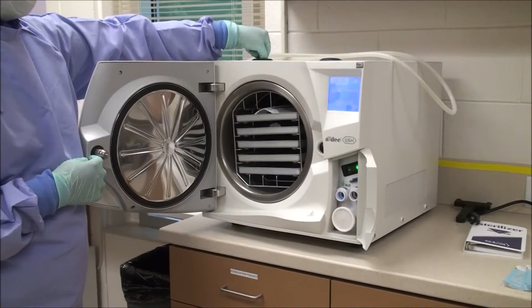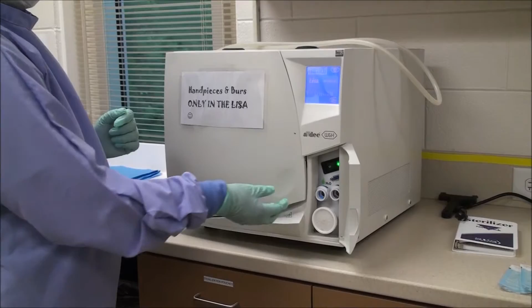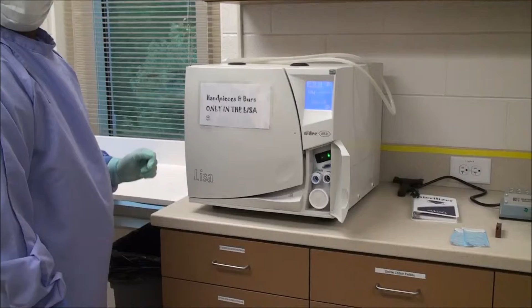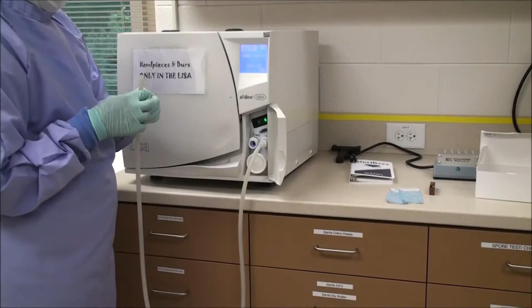Close door and follow touchscreen prompts to select a cycle. For instruments and handpieces, select the higher temperature cycle. Continue with prompts to start the cycle. When the cycle has ended, use the touchscreen to release the door and put the machine on standby. Allow the contents to cool slightly before putting away. To drain the water, put the drainage hose in the Lisa, and place the other end in the bucket.